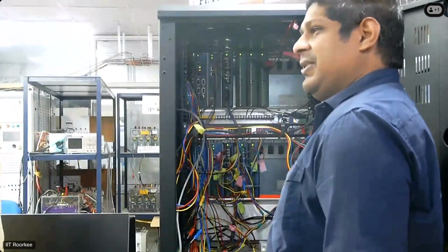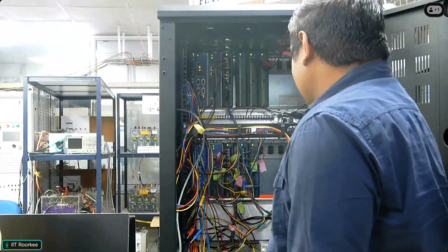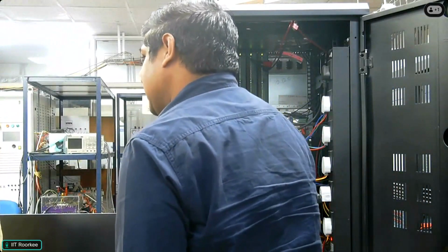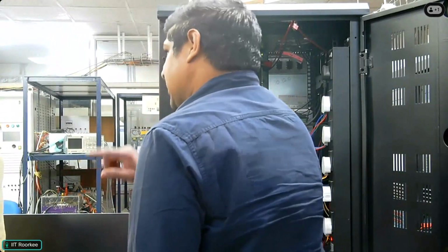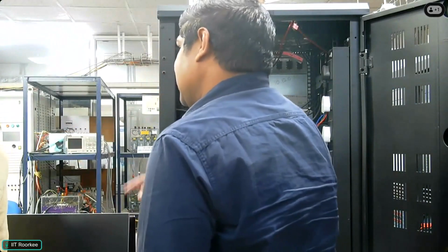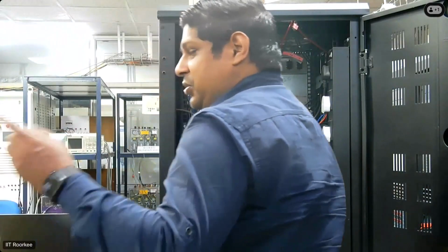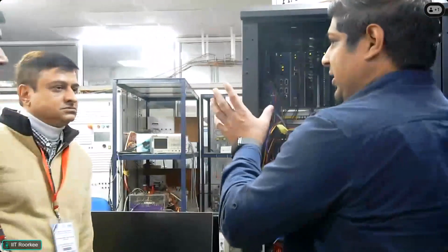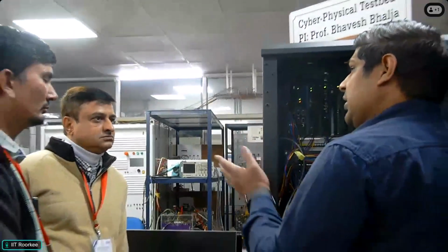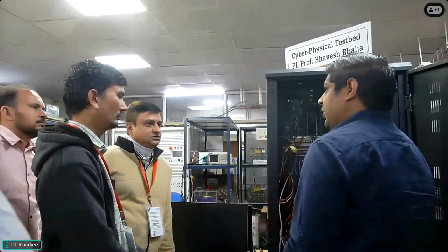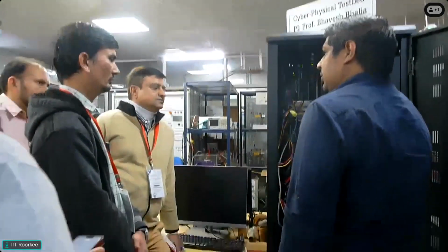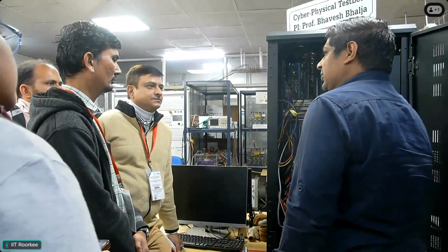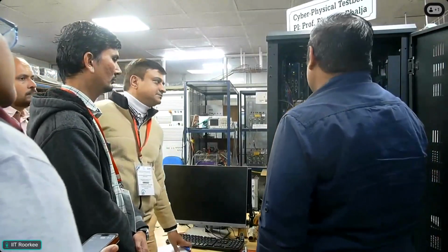Any doubts? Why is the GTSync card required to time sync with the RTDS? It is for the software PMUs or virtual PMUs. How many virtual PMUs can we configure? I will show you. There are 2 blocks, one is GTNET-PMU 8, so there 8 PMUs we can configure. There is also 24, so at a time 24 we can configure. But mostly in the PDC we can receive only 8, so that is the PDC capacity.